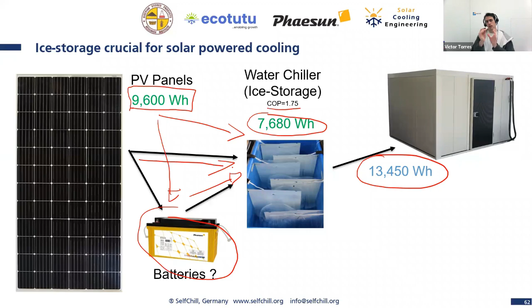We are not working totally battery free, because then you would need a lot of cooling units, since the amount of hours you can run the system would be only around 6 to 7 hours. But we have small batteries that allow us to run the cooling units at night also for a couple of hours. Let's look at how we can deal with this.